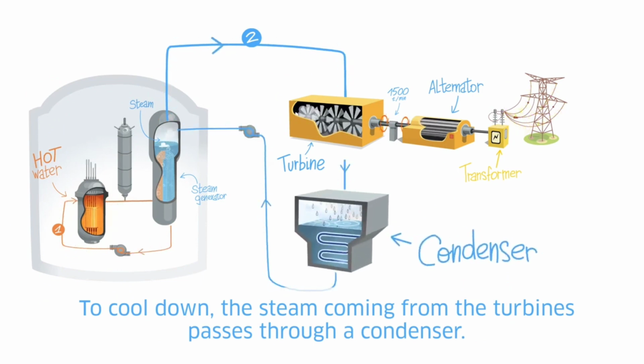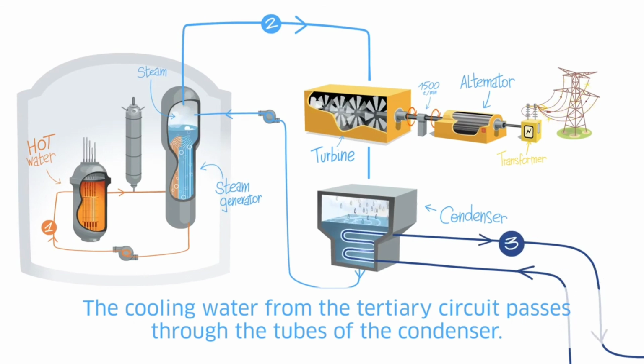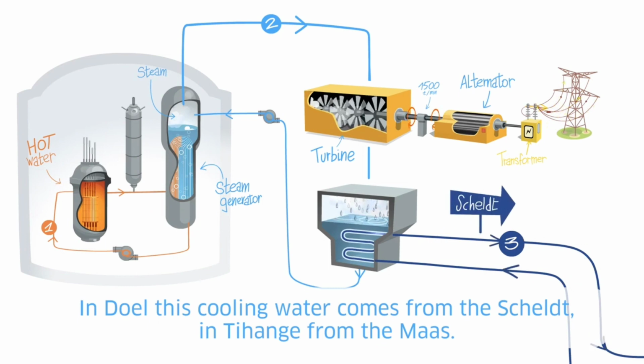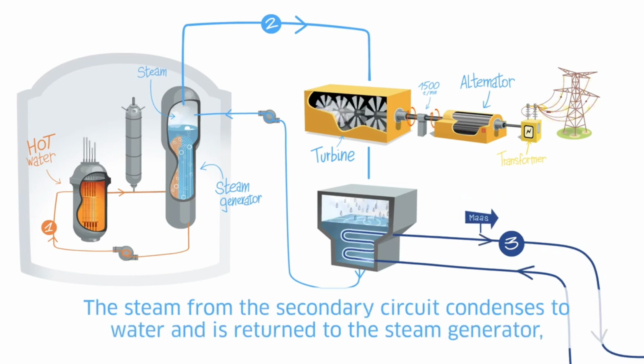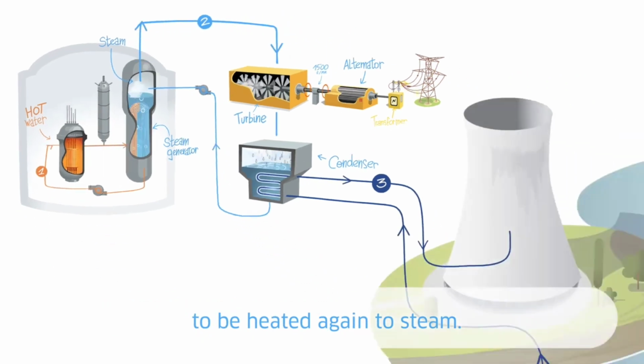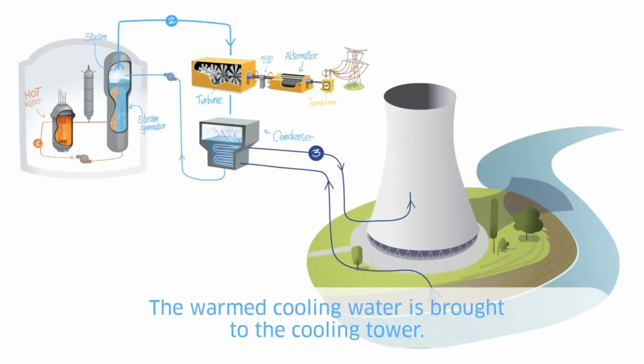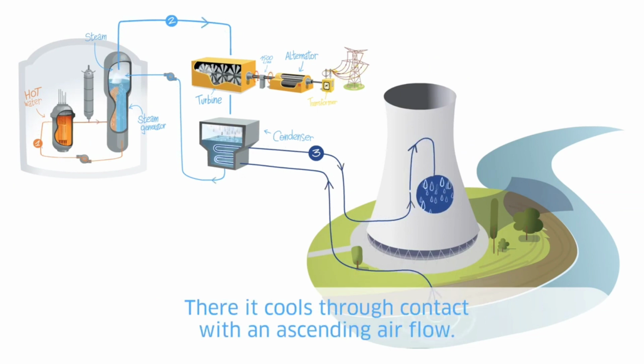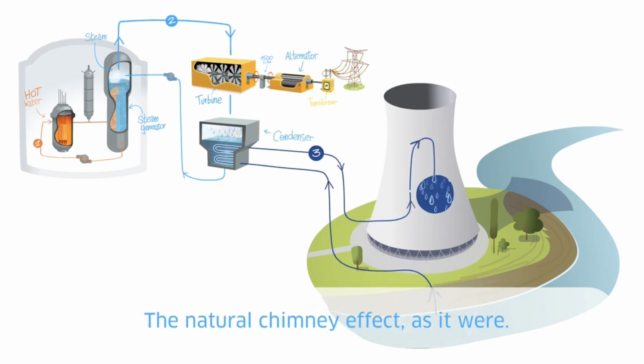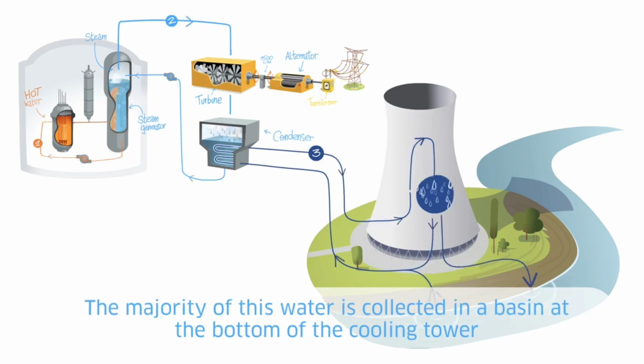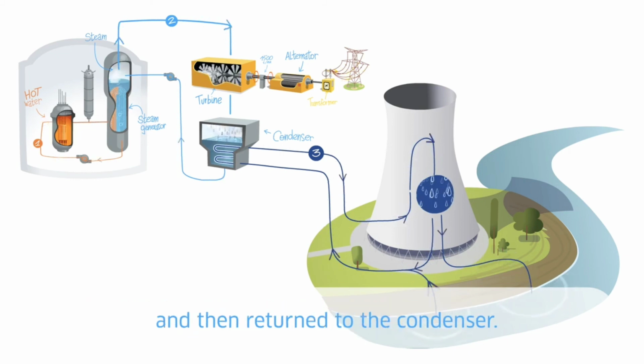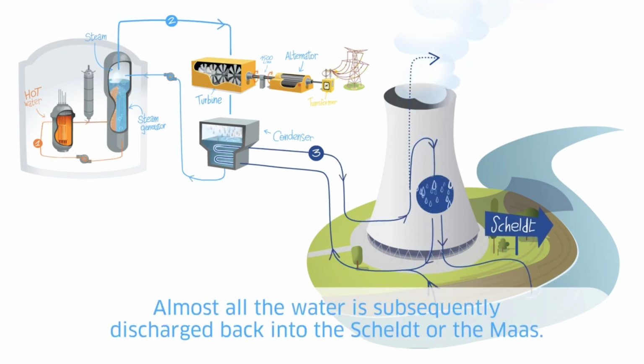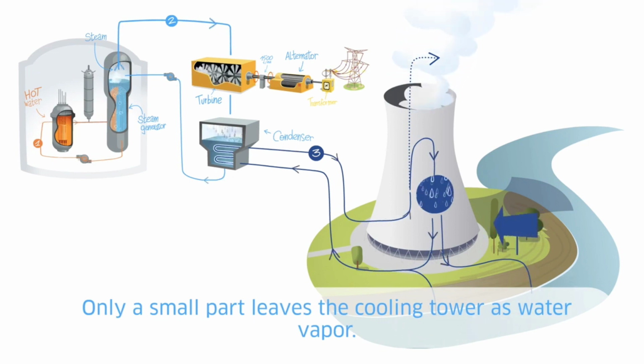To cool down, the steam coming from the turbines passes through a condenser. Cooling water from the tertiary circuit passes through the tubes of the condenser. In Doel, this cooling water comes from the Scheldt and in Tihange from the Meuse. The steam from the secondary circuit condenses to water and is returned to the steam generator, to be heated again to steam. The warm cooling water is brought to the cooling tower. There it cools through contact with an ascending airflow, the natural chimney effect as it were. The majority of the water is collected in a basin at the bottom of the cooling tower, and then returned to the condenser. Almost all the water is subsequently discharged back into the Scheldt or the Meuse. Only a small part leaves the cooling tower as water vapor.